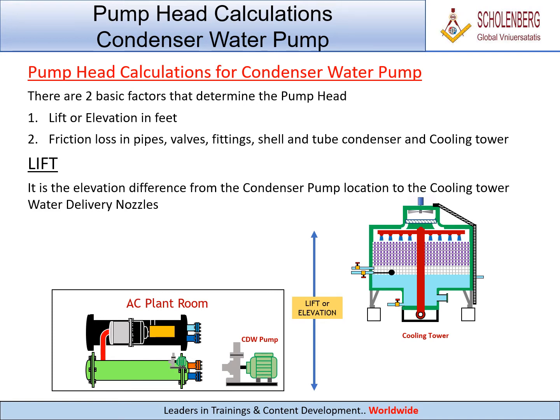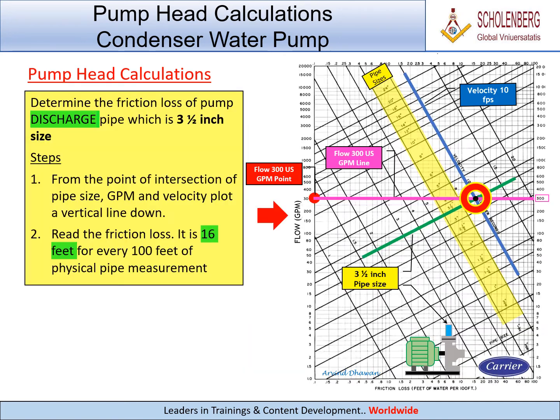Lift is the elevation difference from the condenser pump location to the cooling tower water delivery nozzles. To determine the friction loss of the pump discharge pipe (3½ inch size): 1. From the point of intersection of pipe size, GPM, and velocity, plot a vertical line down. 2. Read the friction loss — it is 16 feet for every 100 feet of physical pipe.